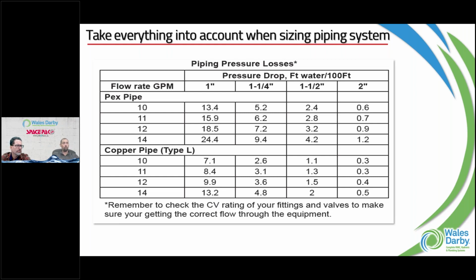So if I bumped it up to 1.25-inch pipe, a little bit harder to work with, maybe a little more cost, to move that same 10 GPM the pressure drop's only 5 feet of head compared to 13. That's a pretty considerable drop right there, and maybe a big drop in price for the circulator you might have to use to pump that water through there. And then even drop it from PEX to copper.